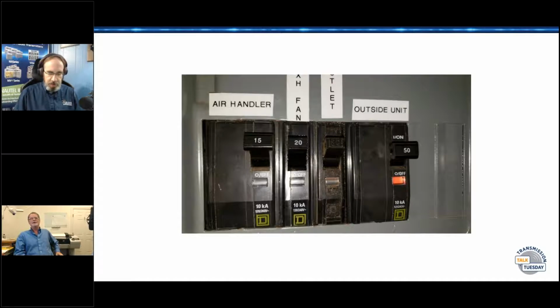The software that they have for it is fantastic because you can do the image overlays, which is very handy when you're trying to figure out there's a hot spot on that AC panel, but which breaker is it? Well, if you do that blended image, it'll outline every breaker, and it's good to have when you go back later and go, okay, now I'm having a problem with the breaker. Was it this bad before? And you look back and go, nope, wasn't running this hot before.